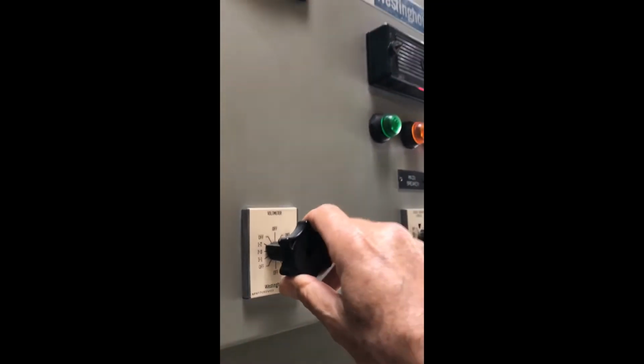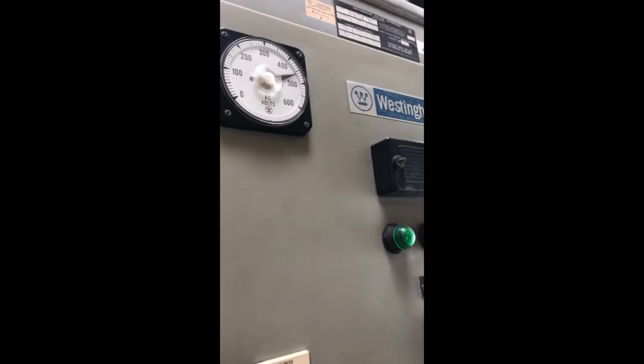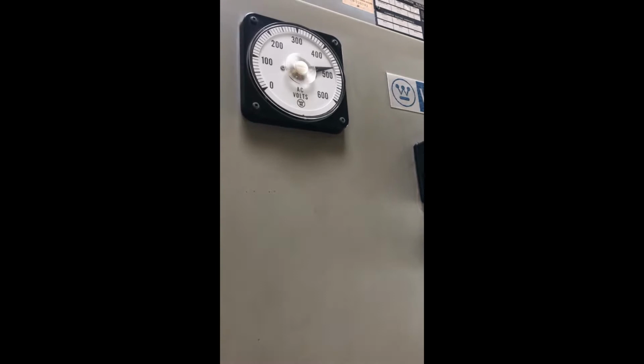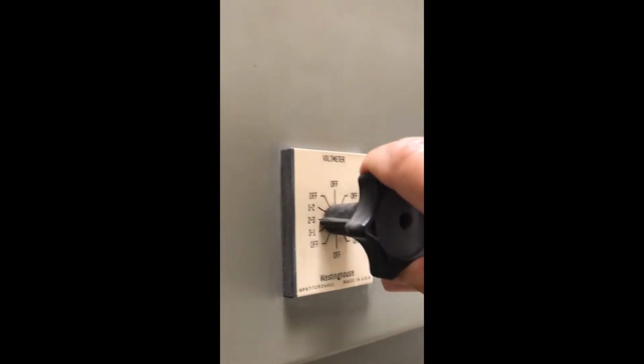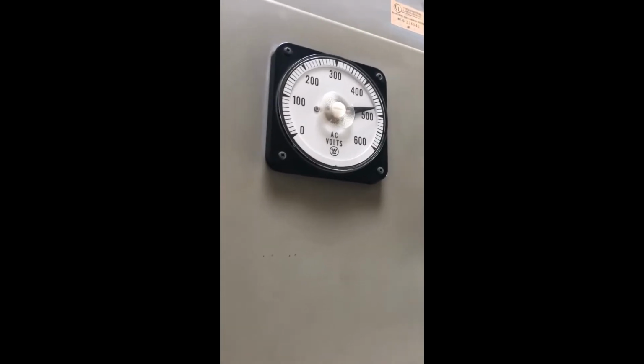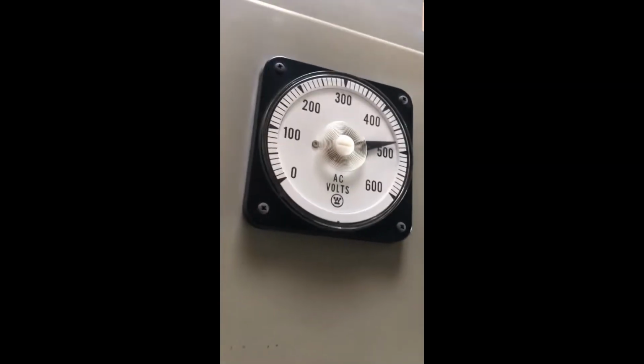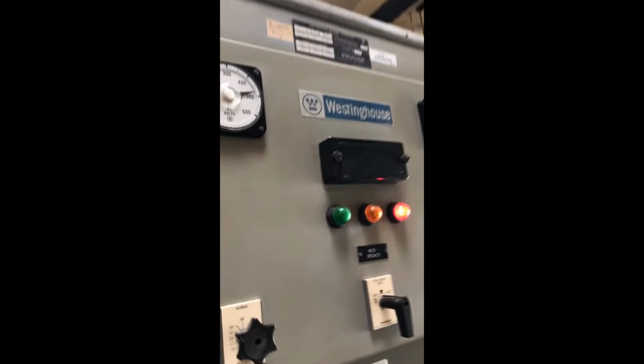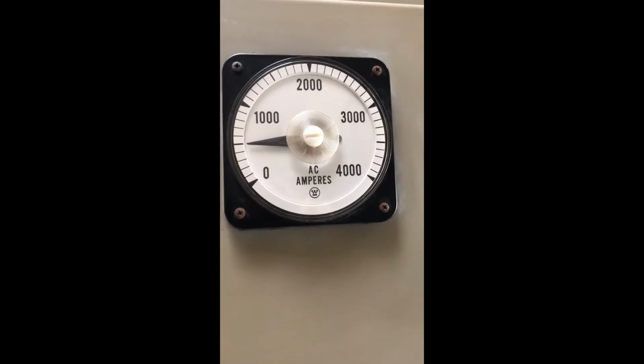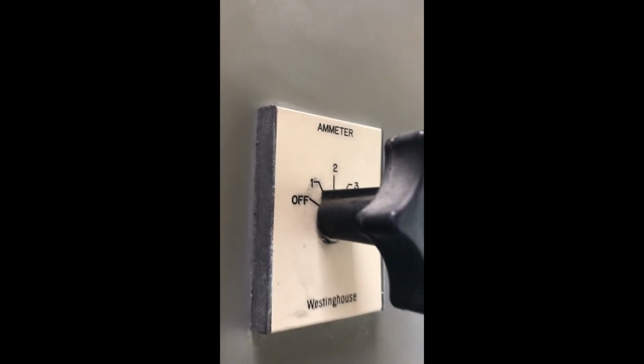So if we go to 2, 3, we're looking at the voltage between B and C. And then 3 to 1, that is the voltage between C and A. So I usually just leave this in between the 1, 2, but you can measure voltage between all three phases, make sure that we got good voltage coming. And then right now at this particular moment, this facility is using about 500 amps. And that should be about the same on A, B, and C.